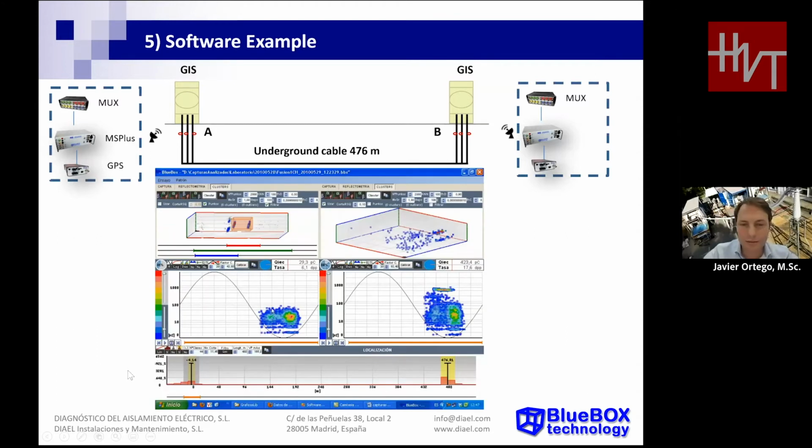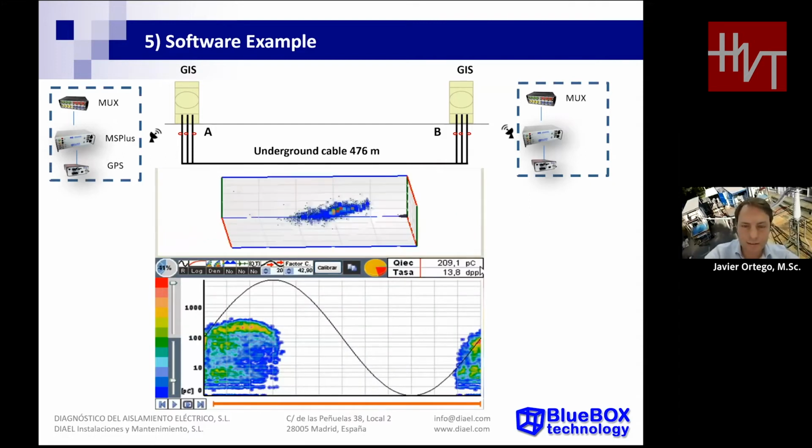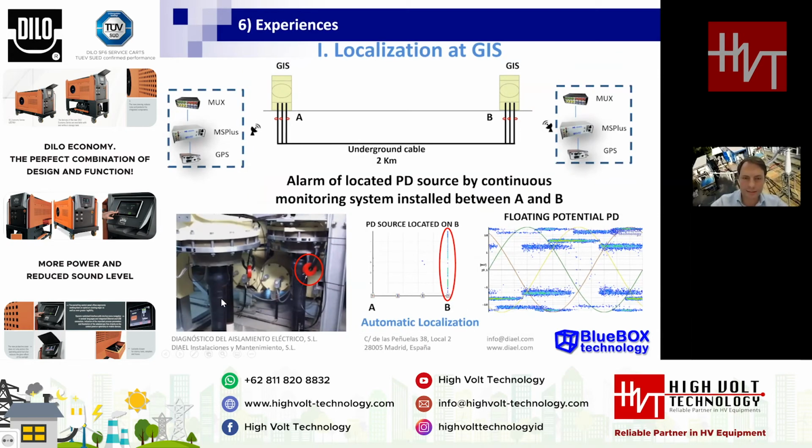Now we go to the other substation, and we will see the pattern of the PDs coming from it. We have in the other substation a PD pattern corresponding to an external surface PD. So we have one cloud, and we don't need to cluster the information in this case because only one PD pattern is represented in this substation. Okay, let's go to the next slide.